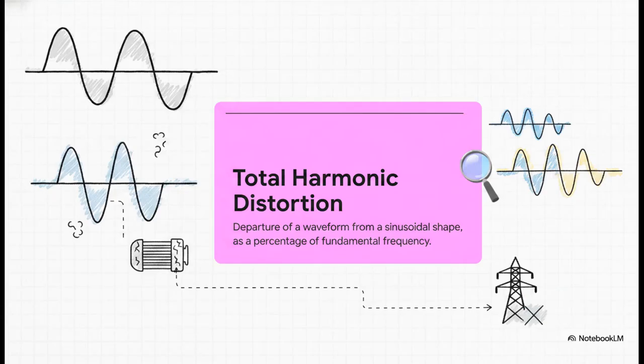We measure that cleanliness with something called total harmonic distortion, or THD. Basically, THD calculates how far your power strays from a perfectly smooth, pure sine wave. This distortion happens when one or more harmonics get added to the fundamental frequency. You can honestly think of it as a type of electrical pollution that quietly but really severely damages equipment over time if we don't keep it in check.